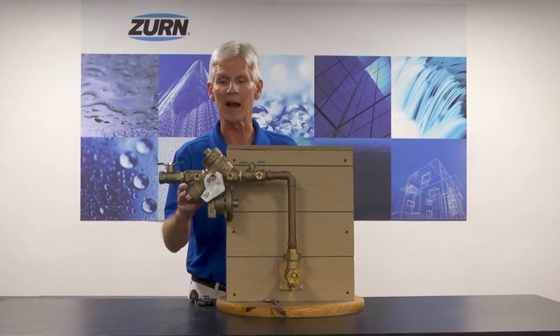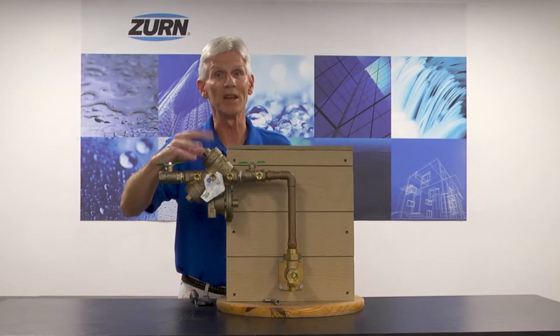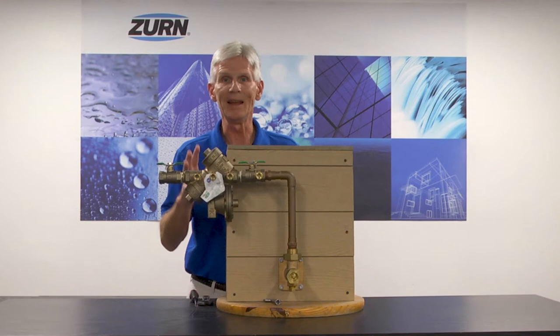So in this particular video, what we're going to do is clean the number one check of a three-quarter inch model 975XL2. Now again, this is a reduced pressure principle assembly. We have found through our diagnosis that the number one check of this valve is fouled, and that's what's causing the relief valve discharge.